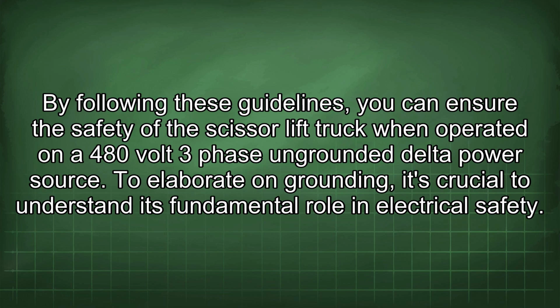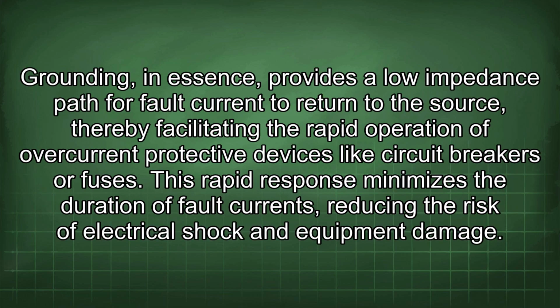ungrounded delta power source. To elaborate on grounding, it's crucial to understand its fundamental role in electrical safety. Grounding, in essence, provides a low-impedance path for fault current to return to the source, thereby facilitating the rapid operation of overcurrent protective devices like circuit breakers or fuses. This rapid response minimizes the duration of fault currents, reducing the risk of electrical shock and equipment damage.